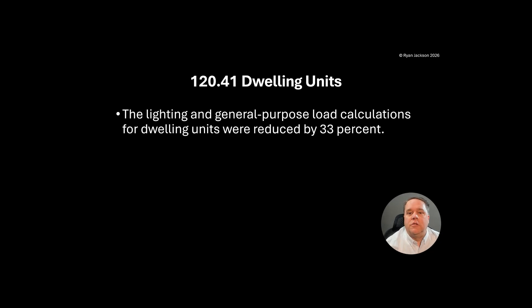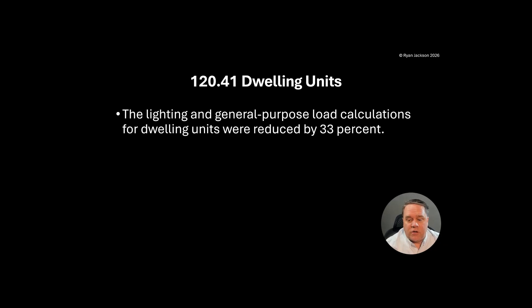Exactly what it sounds like — we reduced the load calculation for dwelling units. Back in the 2020 code, they went through and reduced a bunch of the lighting load calculations for all different occupancies throughout the NEC, except for dwelling units. The reason was the task group said it's basically a one-year window in the code revision process, so they decided to tackle non-residential first.